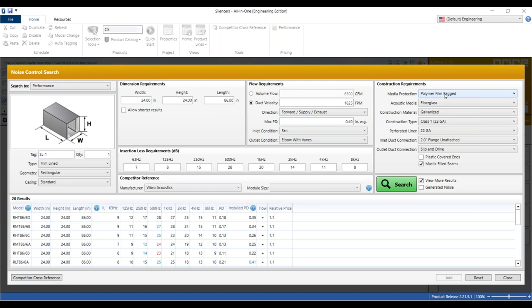So whenever you see a schedule or you grab a silencer out of the catalog and you grab a regular absorptive silencer performance, but then add a note that says must have polymer film liner, then that doesn't really apply anymore, because it's going to have different performance. Okay, just wanted to mention that. And the polymer film silencer is equivalent to what you might hear as Mylar or Tedlar. Mylar and Tedlar is just a brand name. The polymer film liner silencer from Price is equivalent to that.